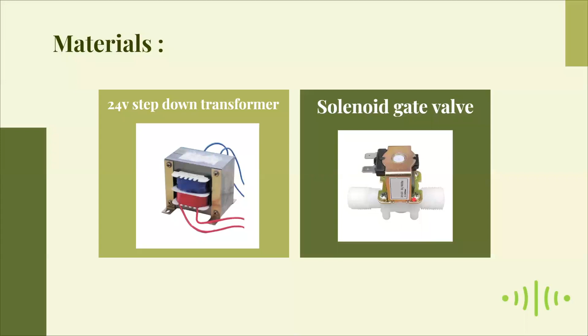A solenoid valve controls the flow of liquids or gases, operating in a fully closed or fully open mode. They are often used to replace manual valves or for remote control. The solenoid valve function involves either opening or closing an orifice in the valve body, which allows or prevents flow through the valve. A plunger opens or closes the orifice by raising or lowering within a sleeve tube when the coil is energized.